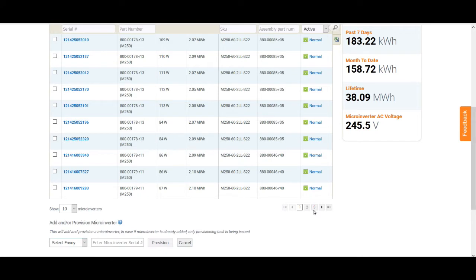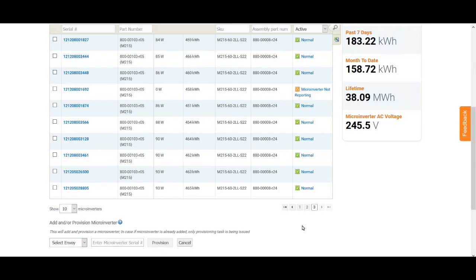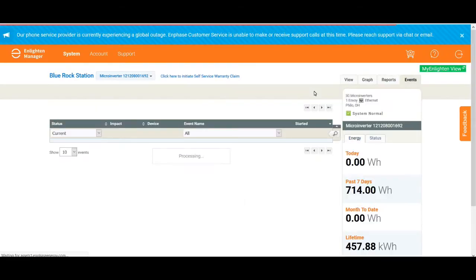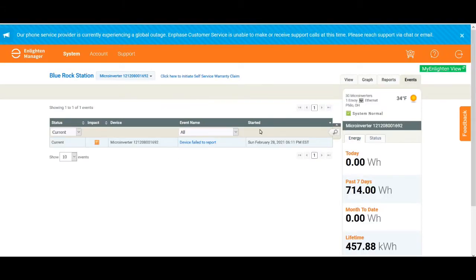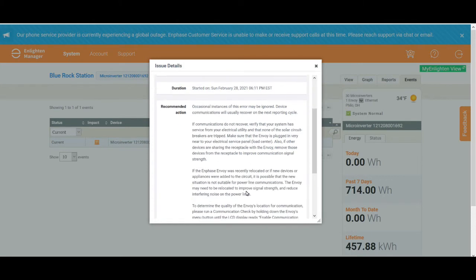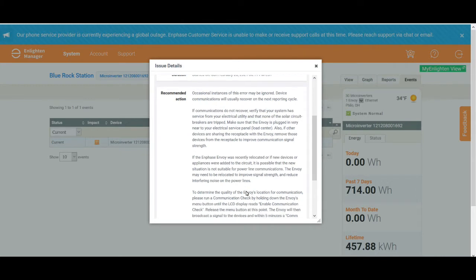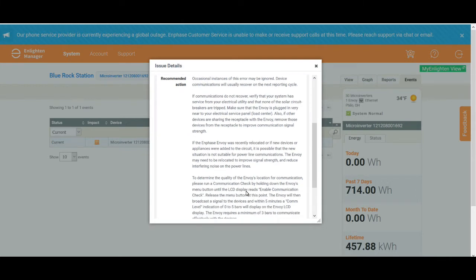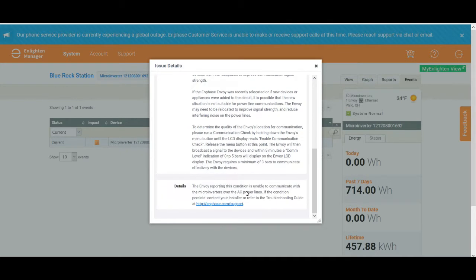I received an email telling me that the inverter was bad. I went online to the Enlighten system and I determined that it was in fact one of the microinverters had gone bad. The system is pretty good about telling you - you can click on it and it gives you a whole bunch of information about what's going on with that particular inverter.